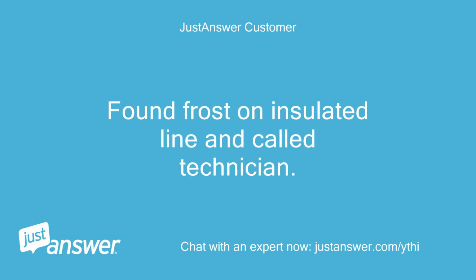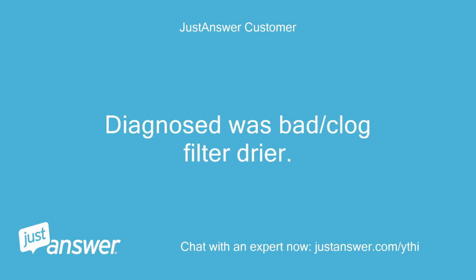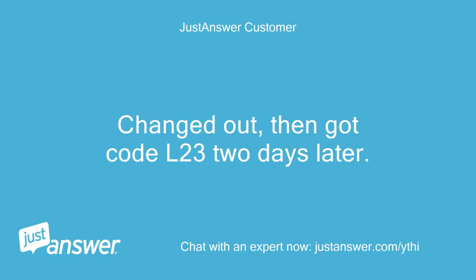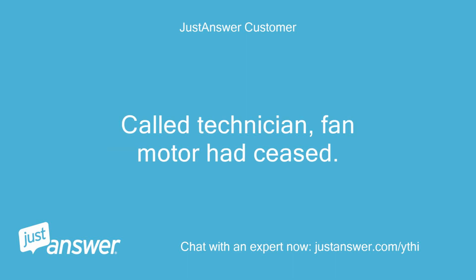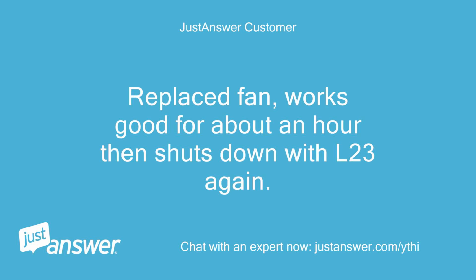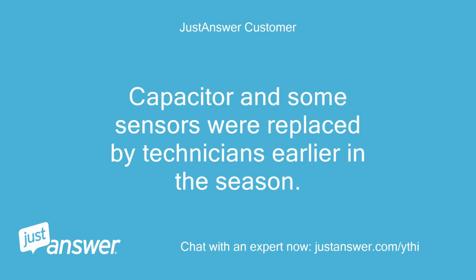Found frost on insulated line and called technician. Diagnosed with bad/clog filter dryer. Changed out, then got code L23 2 days later. Called technician, fan motor had ceased. Replaced fan, works good for about an hour then shuts down with L23 again. Capacitor and some sensors were replaced by technicians earlier in the season.